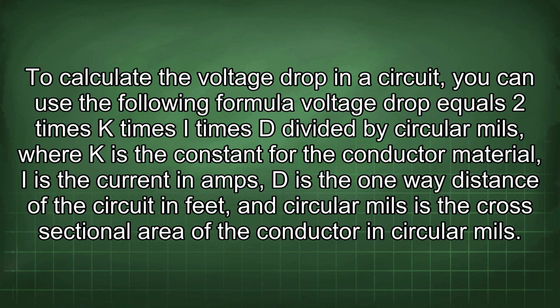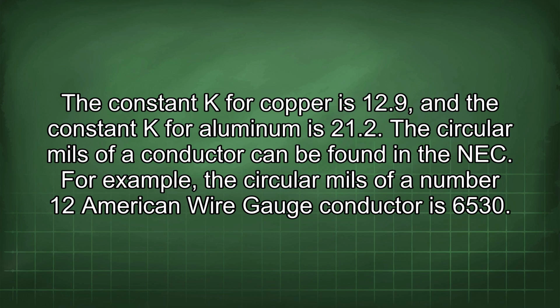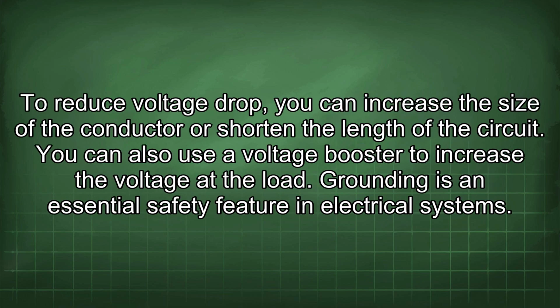To calculate the voltage drop in a circuit, you can use the following formula: voltage drop equals 2 times K times I times D divided by circular mils, where K is the constant for the conductor material, I is the current in amps, D is the one-way distance of the circuit in feet, and circular mils is the cross-sectional area of the conductor in circular mils. The constant K for copper is 12.9 and the constant K for aluminum is 21.2. The circular mils of a conductor can be found in the NEC. For example, the circular mils of a number 12 American wire gauge conductor is 6,530. To reduce voltage drop, you can increase the size of the conductor or shorten the length of the circuit. You can also use a voltage booster to increase the voltage at the load.